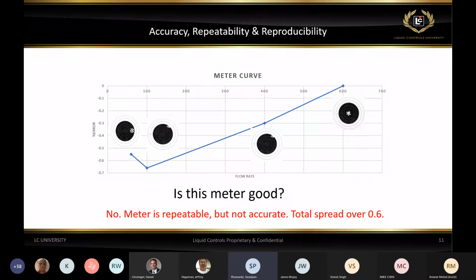That generally may not be acceptable in all the requirements. So is this meter good? At high flow, yes. Overall total spread is a little bit high. This would probably be a typical curve for a meter that's a little bit older, a meter that's been in the field for a long time, and most likely the internals are a little bit extended, causing extra slippage of product through the meter. So even though it's accurate at high flow, and repeatable, at the low flow this meter will not meet the requirements. Again, typical for an old meter, a little bit worn out internally.